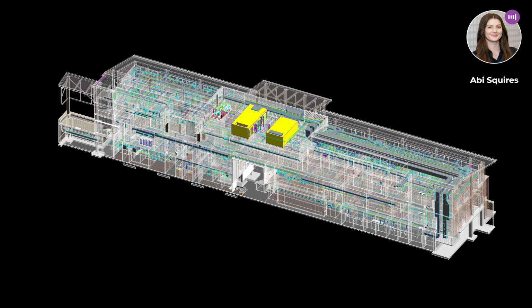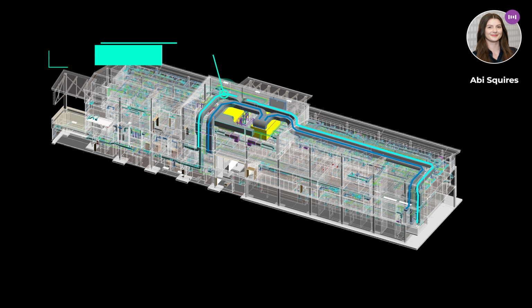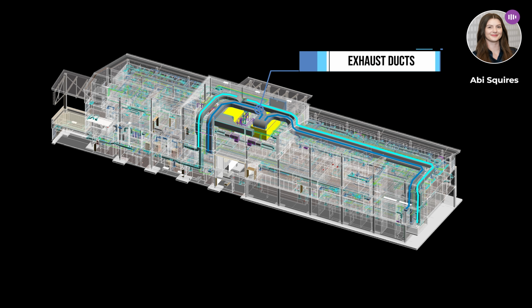It is important to consider a clearance zone around the equipment to allow for standard maintenance procedures. Supply ducts shown in the cyan-colored lines take conditioned air from the unit and move it to different spaces in the building. Vertical main risers distribute at each floor level, and then branches run to individual spaces. Exhaust ducts shown in the darker blue lines remove air from the space. Similar to the supply, there are return vertical risers and branch ducts. This is important to maintain neutral pressure in the building.